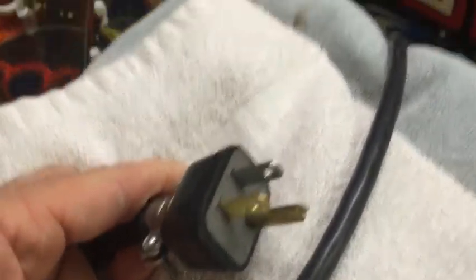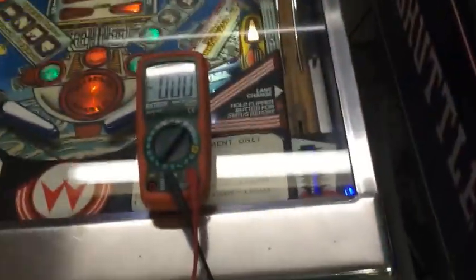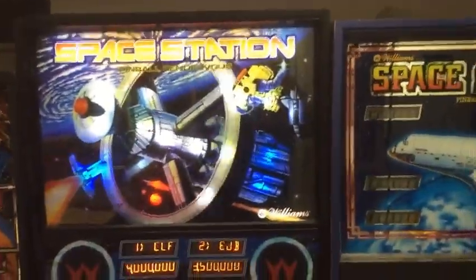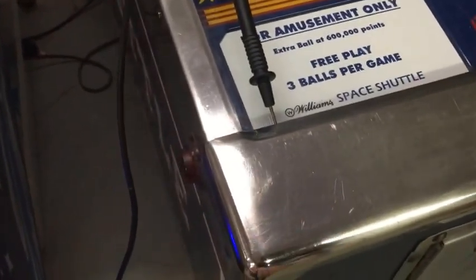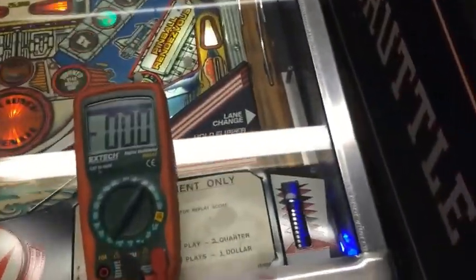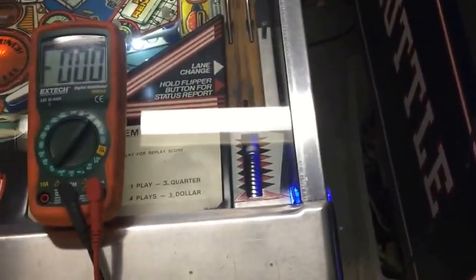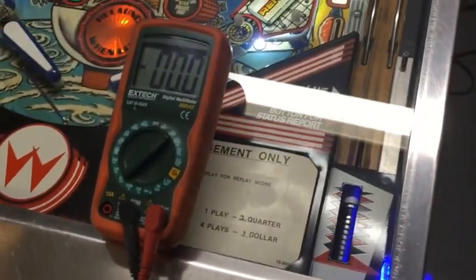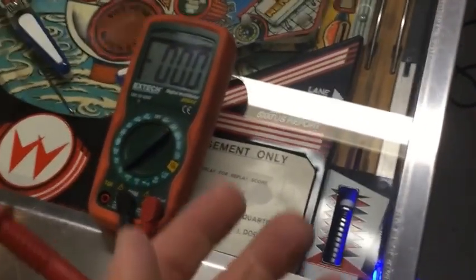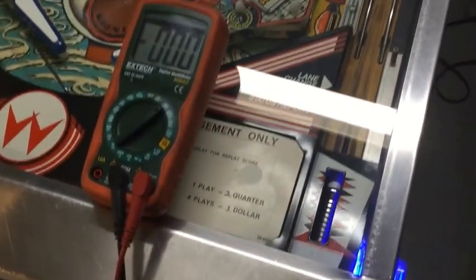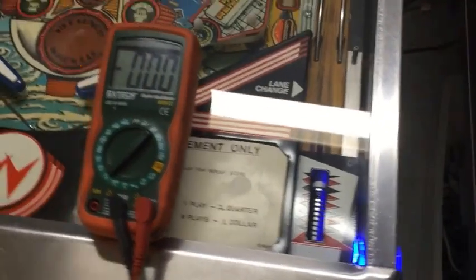We'll see if that fixed our shocking problem on Space Station. So here we are again at the front of Space Station, with Space Shuttle here. We know Space Shuttle has a good ground because we tested it. Remember, we were measuring the AC voltage between the ground plane of this machine and the ground plane of this machine, and before we were getting about 24 volts AC, which I was feeling as a shock. If I had bare feet on the ground, or touched both machines, I'd feel that little AC voltage.